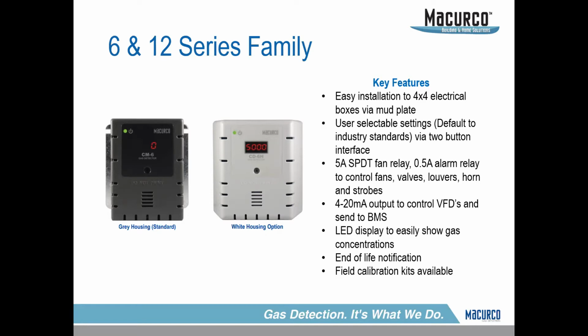But on each of these detectors, you have 2 dry contact relays. One's a 5 amp, one's a 1/2 amp. The 5 amp is for a low alarm. The 1/2 amp is for high alarm. Typical installation on these 2 is a low alarm is going to be tied to your fire panel. And then the 1/2 amp alarm or the high alarm is going to be tied to another zone in your fire panel for your emergency protocols, which is evacuation, fire department, whatever.